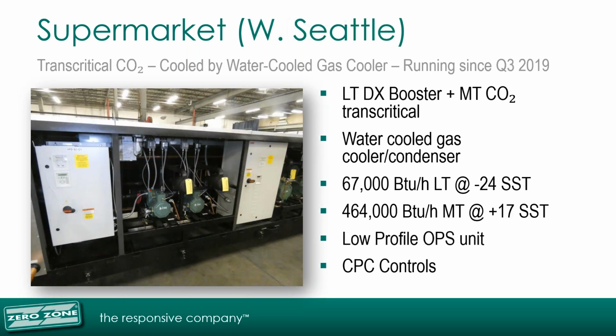Here's another CO2 transcritical booster system with a water-cooled gas cooler/condenser. A low-profile design was needed to meet the space requirements of the building. As seen in these first 3 examples, split suction rack systems can service part of or an entire store, depending on the size of the store.